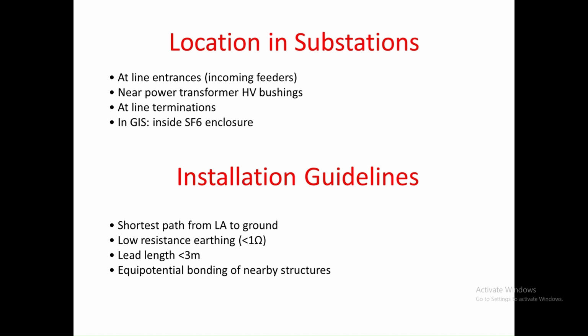So what is the location in a substation? As I said, it is there at the entrance of the line, for which the equipment needs to be protected at the incoming and the outgoing. Similarly, near the transformer bushings, line terminations, and inside the SF6 enclosure for GIS substation, that is the gas insulated substations. And the guidelines are that we should have the shortest path from LA to the ground, low resistance earthing, lead length should be less than 3 meters, and equipotential bonding of nearby structures.